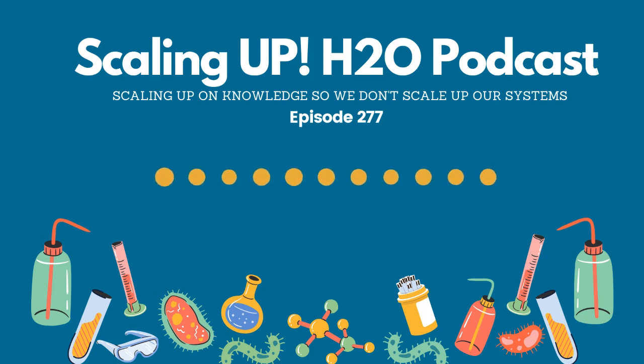Is there a secondary makeup source? Is there a leak in the basin? How much water is lost due to the backwash of a side stream filter? Is the blowdown valve closing all the way? Take this week to think about the mass balance around a cooling tower system and what you may have seen or could see.